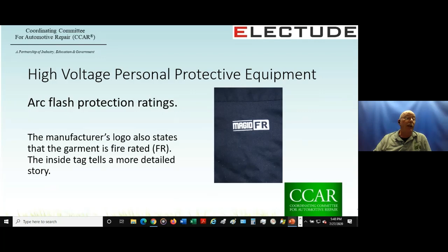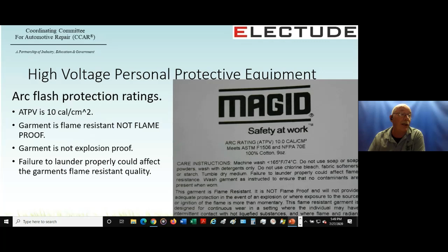The ATPV is 10 calories per square centimeter. The garment is flame resistant, not flame proof. And the thing that killed me was that in the bottom, and you probably can't see it, this garment is not explosion proof. I would have never thought that this garment was explosion proof, but my mistake. And as always, washing it incorrectly is going to be a problem because it's going to reduce protection value.